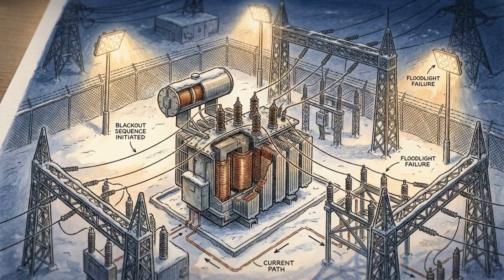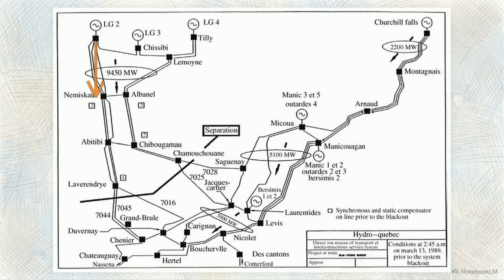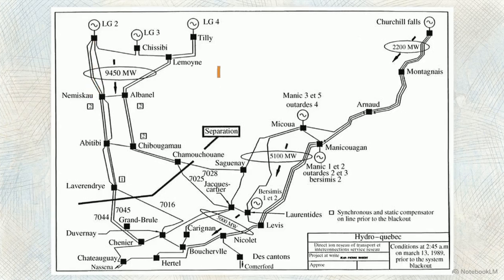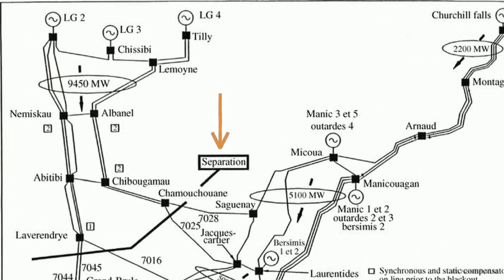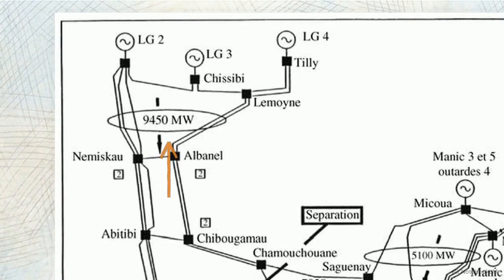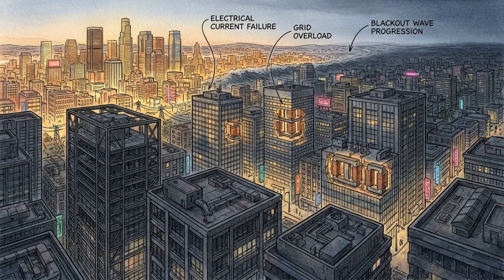The collapse was nearly instantaneous. In less than a minute, 7 critical static VAR compensators were tripped offline by their own protection logic. Without the SVCs to regulate voltage, the system fell out of step. This map shows the result: the separation of the La Grande network from the rest of the province and the immediate loss of over 9,000 megawatts of power. The entire province of Quebec was plunged into a blackout that lasted more than 9 hours as engineers worked to restore the system.